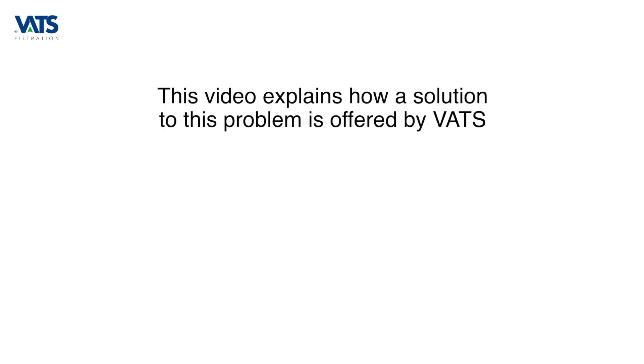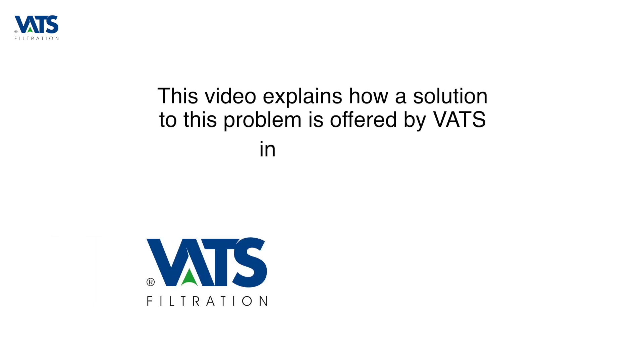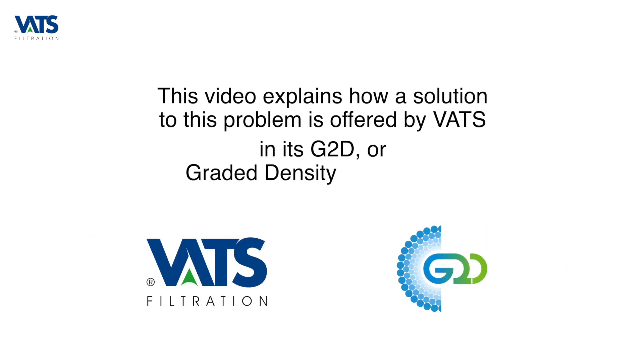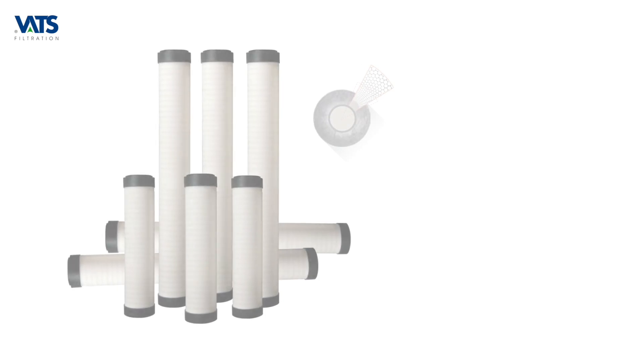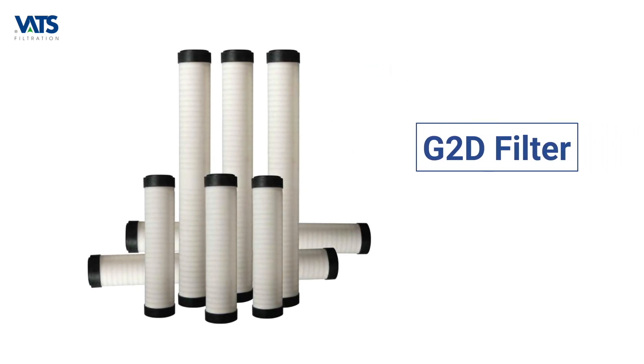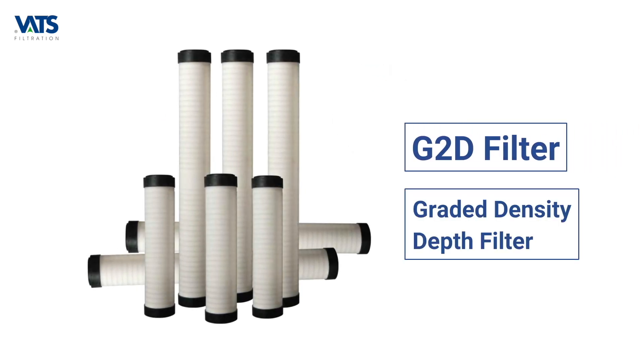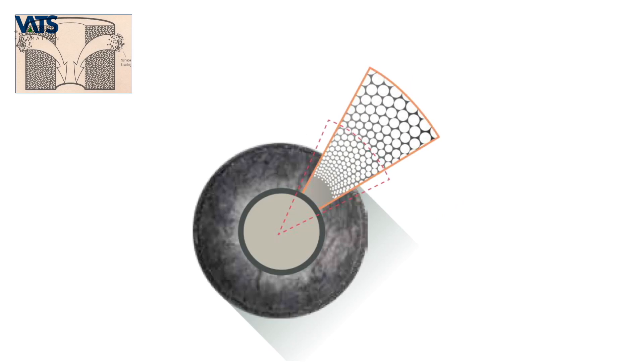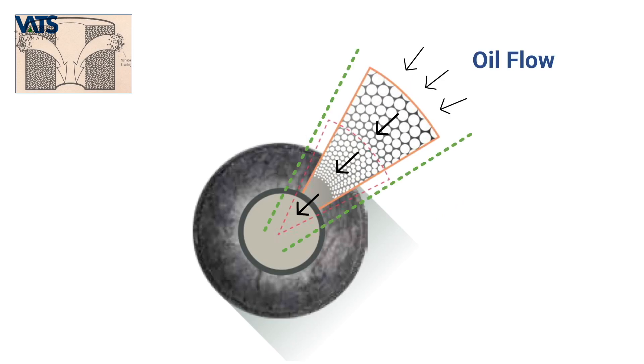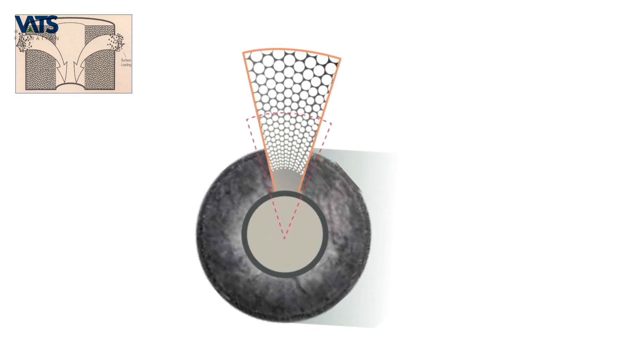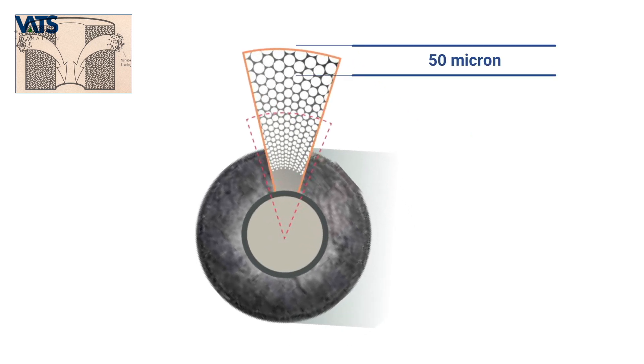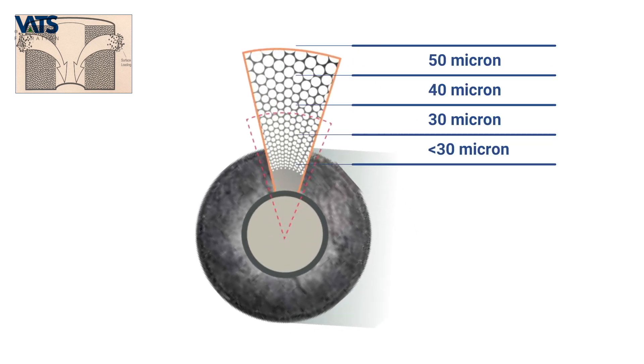The G2D is a graded density depth filter. In its G2D design, VATS presents a filter with its micron size reducing gradually in the direction of flow. Thus the outermost surface can begin with 50 microns, reducing down to just 2 microns on the inner face.